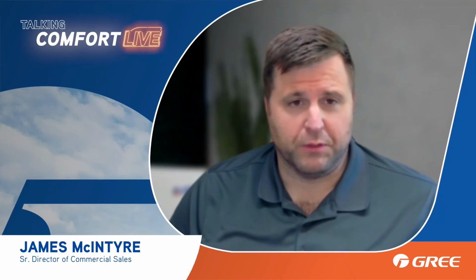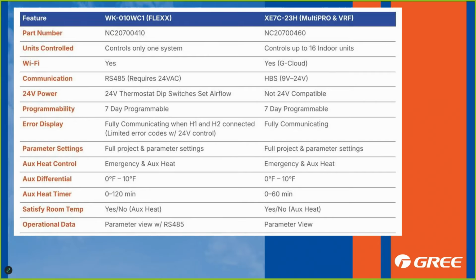Satisfied room temp is another one - that's an option a lot of people like to have, a lot of people want to decide on. Do you want to run your aux heat until you've caught all the way back up? That needs a little more context - it has to go into auxiliary heat, electric heat has to be on before it's going to stay in and satisfy.